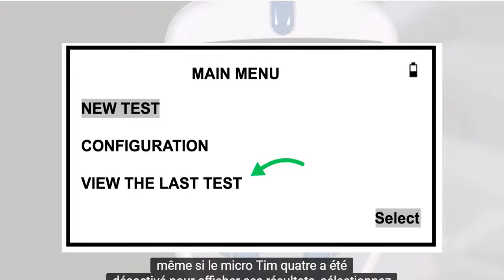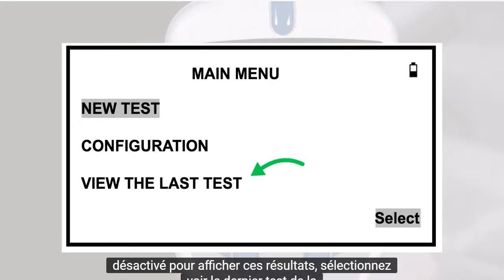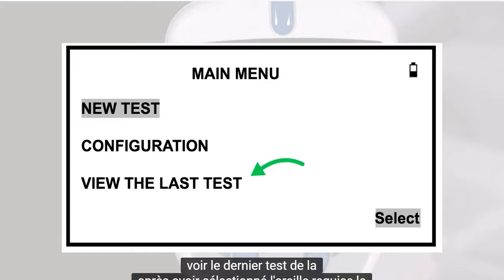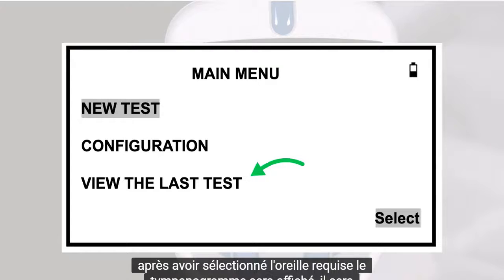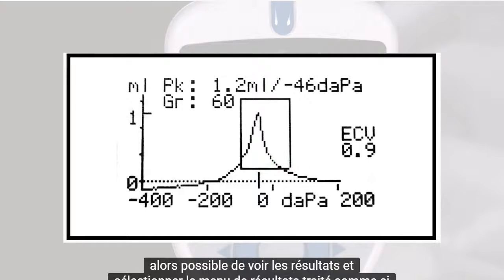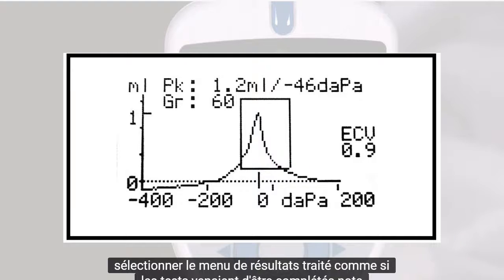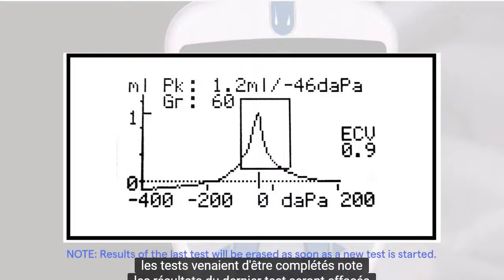To view these results, select View the Last Test from the main menu. After selecting the required ear, the tympanogram will be displayed. It will then be possible to view the results and select the Process Results menu as if the test had just been completed. Note: results of the last test will be erased as soon as a new test is started.